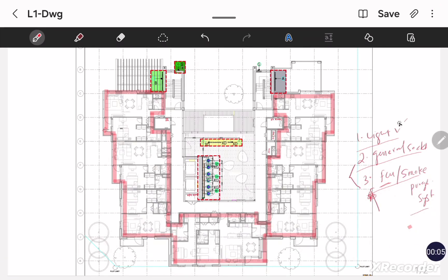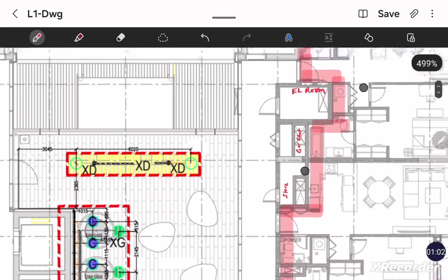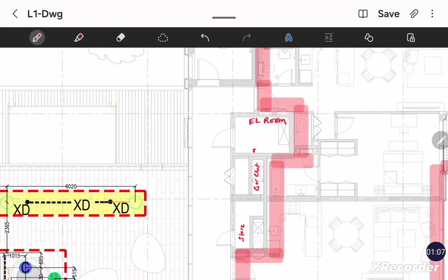Here we will make one separate DB for the light load and one separate DB for the power load. The reason is the light DB has interfacing with the lighting control panel. If we merge all the loads together it will not be recommended by DEWA. If the light loads are not interfaced with the lighting control panel, DEWA does allow one DB for all loads. But as the client requires a lighting control system for the common area, we cannot merge light load with power load. So here in the first floor electrical room we will have two separate DBs: one for power and one for light.